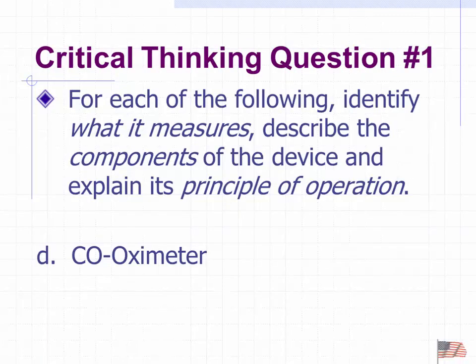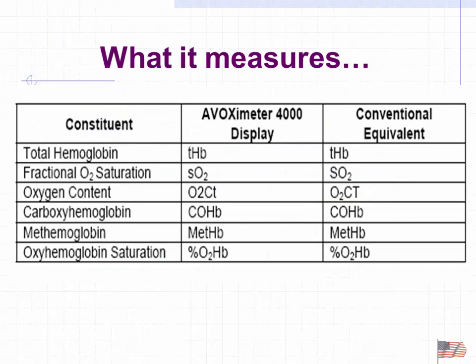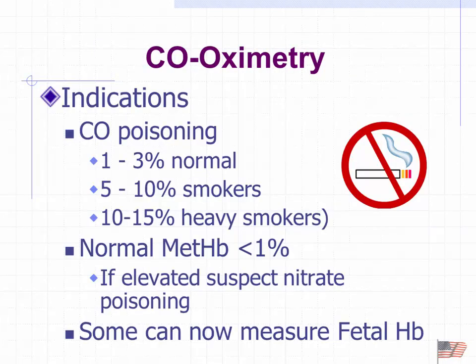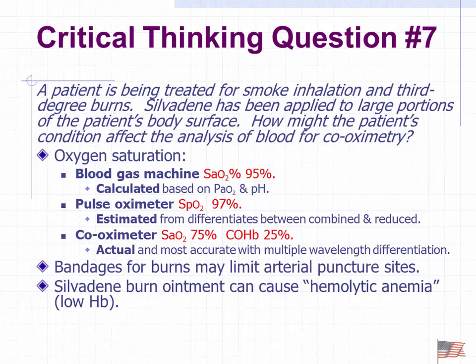Okay. So you should have an idea of how that CO oximeter works, very similar to the pulse oximeter, shining various wavelengths of light to get our values. The other thing you want to remember is that in the presence of smoke or combustion, it's not going to be an accurate reading using a pulse oximeter. It's why we always want to use a CO oximeter. Also, the methemoglobin in the face of nitrates can cause problems also. Here's 3 different devices. That blood gas machine will estimate a saturation. The pulse oximeter will measure a saturation, but it doesn't include carboxyhemoglobin. The best way, if you got a patient who we suspect a high carbon monoxide level, is that we need to do a CO oximeter.